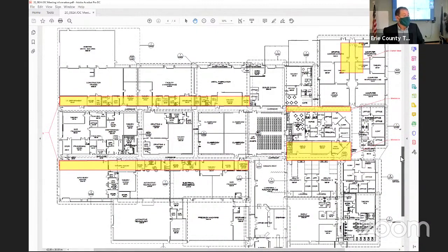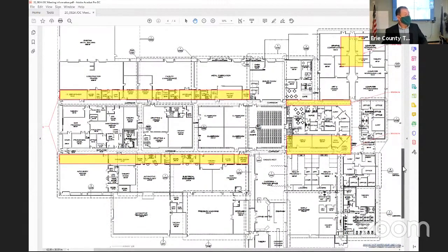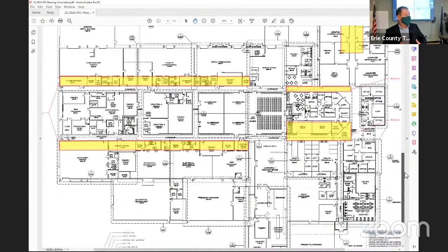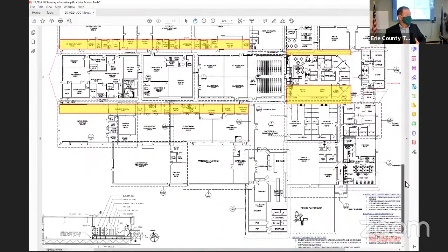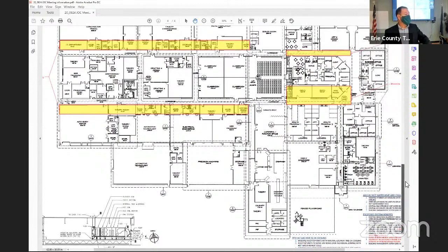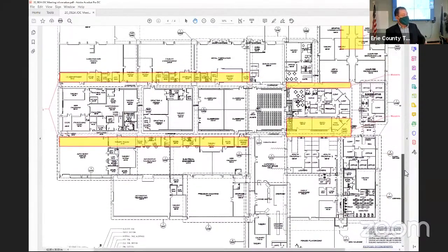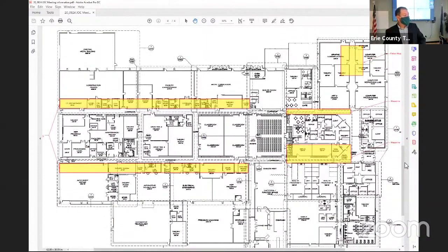There are some positive aspects to rooftop units. The one that comes to mind: if you lose your boiler plant, say you lost all 4 boilers, you would be able to run a rooftop unit at a higher temperature to maintain your space temperature, so you'd have that ability. But we compensate for that in the design of the air handling units by providing redundancy in the boiler plants. So we kind of balance it out that way, so you're not dependent on one piece of equipment.